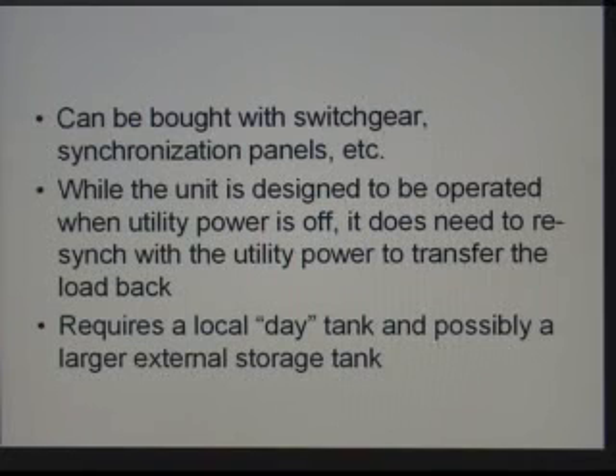But to exercise it, there's also a manual start capability on them so that you can bring them on and offline whenever you need to verify operation, and make sure that maintenance operations you've done haven't compromised the operation of the machine. Okay, it requires a local day tank, possibly a larger external storage tank.